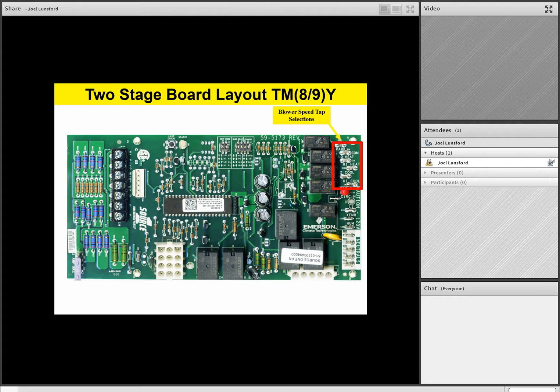So by all means, select those proper speed taps based on your ductwork when you commission the furnace. As we move around, we have a 120 volt EAC terminal. That's for an electronic air cleaner. We put a little red ball on there just to remind everybody it's 120 volt. That CIRC terminal is your 120 volt that feeds the blower motor all the time. Because remember, an ECM motor, a high efficiency motor, has power to it all the time, and then we command it with 24 volt inputs. L1 is where we bring in the 120 volt to power up those components from our power source.